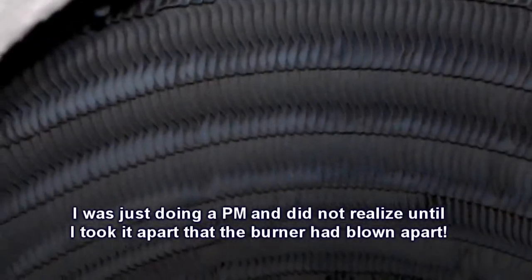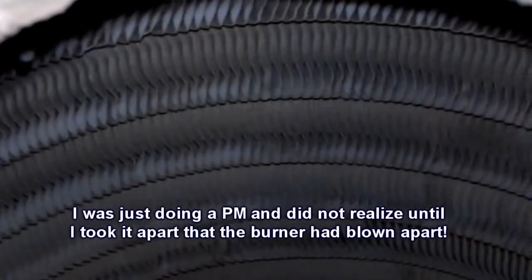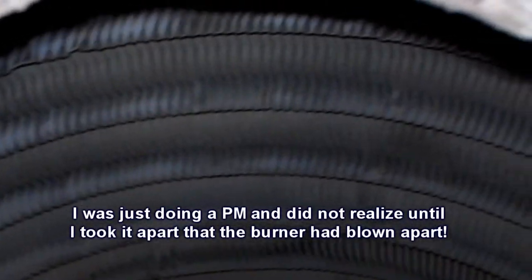Probably could be vacuumed. Oh yeah, there's a piece of metal. It is screwed up. Maybe that's why it's got a little bit of funky sound, like a delayed ignition, even though it's not. But there's your spiral fins for your water tubes. It looks like I probably need a new burner for this A.O. Smith. I didn't even know it. I'm just doing regular maintenance.